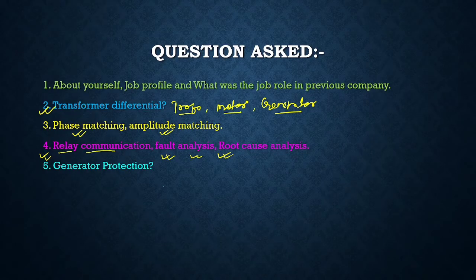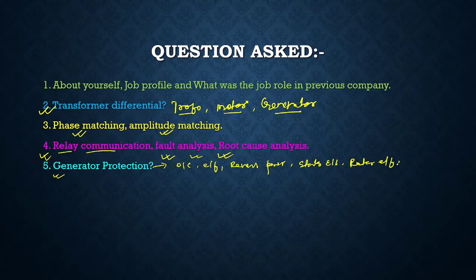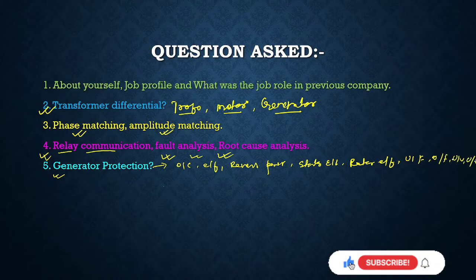The next question was on generator protections. You don't know in which plant they are taking you, maybe a CPP or some other plant, so generators play a very important role. You can study the generator protections: what they are, and what type of protection is used for the generator. You can have overcurrent, earth fault, reverse power, stator earth fault, rotor earth fault, under frequency, over frequency, under voltage, over voltage.